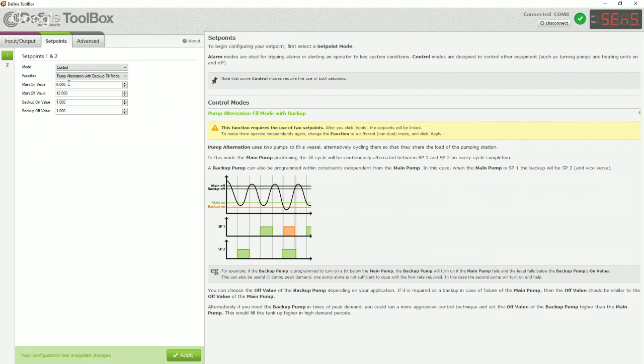So again, we've still got the on value of 6 milliamps. So when the level drops below 6 milliamps, the pump will turn on, and we've got the off value of 12. And what this mode will do for starters is the one pump will turn on, then the next time we go below the limit, the other pump will turn on. But the other feature we can apply on top of that is a backup value. So if I say the pump, whichever pump's turn it is, has to turn on at 6 milliamps, but if it gets as low as 5 milliamps, then we want the second pump to turn on as well, and that means that the second pump can act to share the load. So if you have a scenario where the load changes sometimes, and most of the time only one pump is enough, but sometimes you need two, then this is ideal for that application.